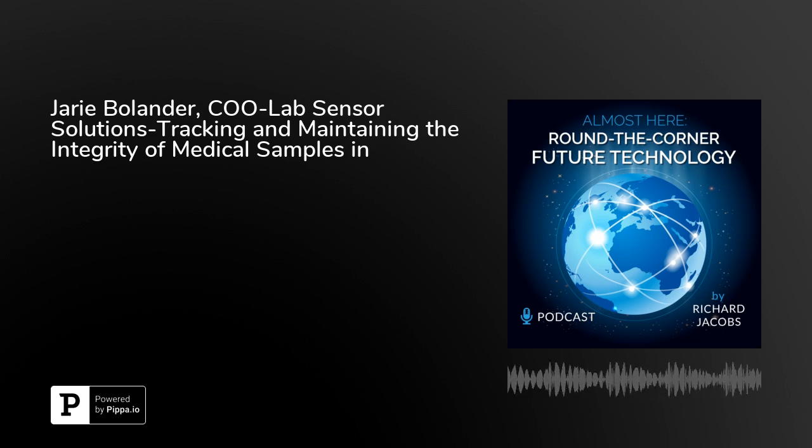So what has this done to the error rates? How many couriers do you have this out to, and what have you seen in the error rate reduction? Yeah, we have about a dozen customers all around the country. And what we found is that within about 2 to 3 days, we can get the amount of excursion of temperature to go down. Before measuring it's hard to measure, but we see correction anywhere from 3 to 5 times a day, depending on the temperature, during an 8-hour shift. Whereas before there would be no corrections because no one would know.